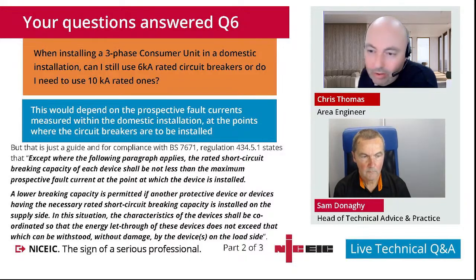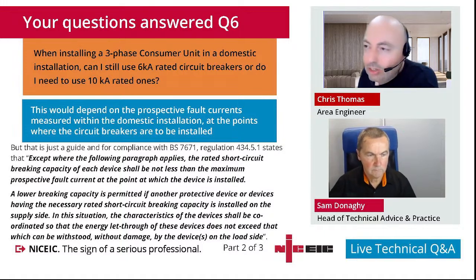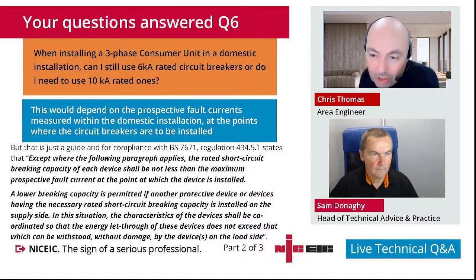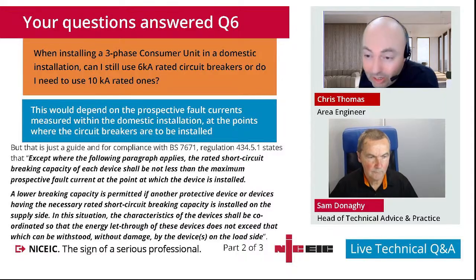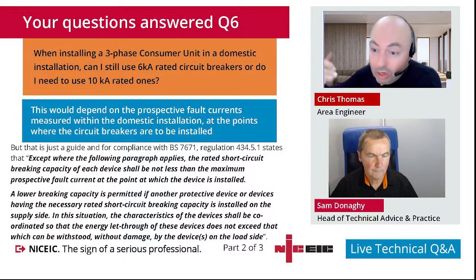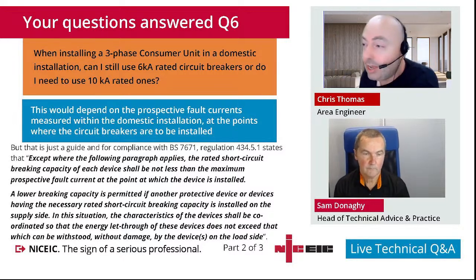So when you see three-phase, most people start thinking, oh, it must be large current demand, large loads. That's not necessarily the case, and it would have to be assessed correctly in the usual way. And Chapter 43 would help us with that. There's also a little bit of information in Appendix 14, but Chapter 43 is going to be a good starting point to assess that. There are some exceptions to the rule where we can exceed that rating, but generally speaking, we'd have to assess it, make sure the breakers are suitably sized based upon the fault current, and then we would be able to determine whether we do need to bump that up to a 10 kA rather than a 6 kA.